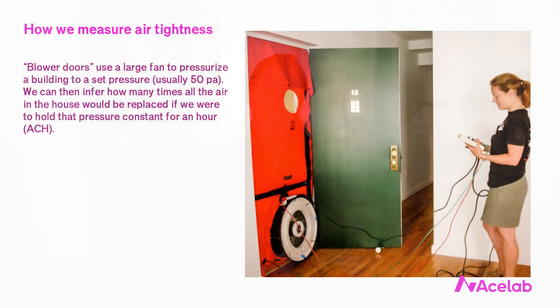Blower doors are large fans that we use to pressurize a building to a set pressure, usually 50 pascals. We then infer how many times all of the air in the building would be replaced if we were to hold that pressure constant for an hour. This is referred to as the air change per hour, or ACH, at 50 pascals. For reference, 50 pascals is about the pressure created by a 20 mile per hour wind.